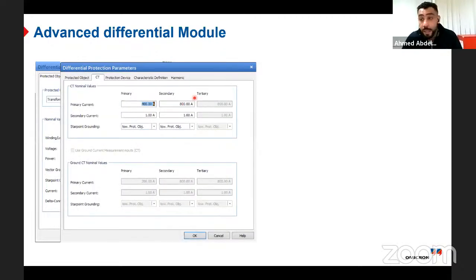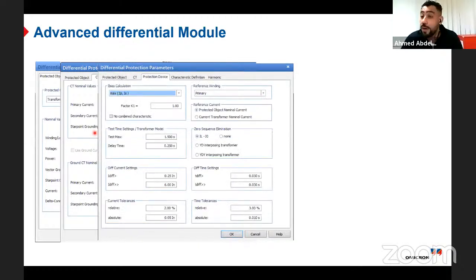Afterward, I need to define my CT, the high voltage CT, the low voltage CT, and also the most important parameter we talk about, which is the polarity of the CT. If my CT is toward the object, it means P2 to P1 is toward the object or the other side. This can happen in star point grounding applications. Then I need to define the protected object, which relay I'm testing. For example, as I said, I'm testing a Siemens relay. So in a Siemens relay, you need to define here.